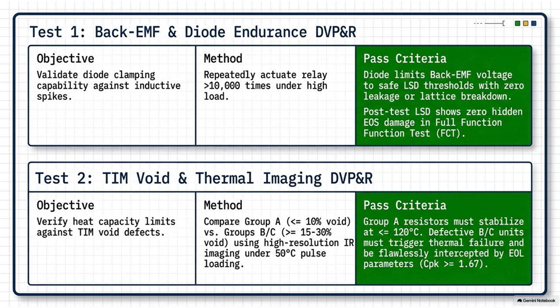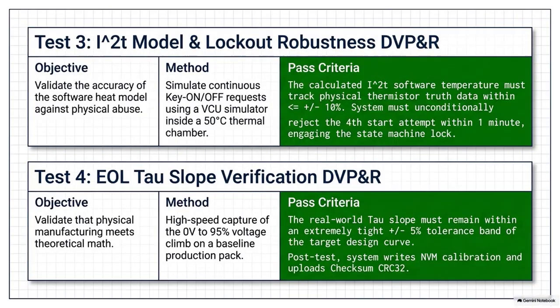Second, on the 4th consecutive pre-charge attempt within a 1-minute window, the software must unconditionally lock the relay. It has to prove it can autonomously deny a start request. Yes. And then they leave the system in that 50-degree oven to observe the cooldown. The software must correctly calculate the degraded thermal convection rate and only safely unlock once it actually cools. Unbelievable. That brings us to torture test 2, the 10,000 cycle whip.